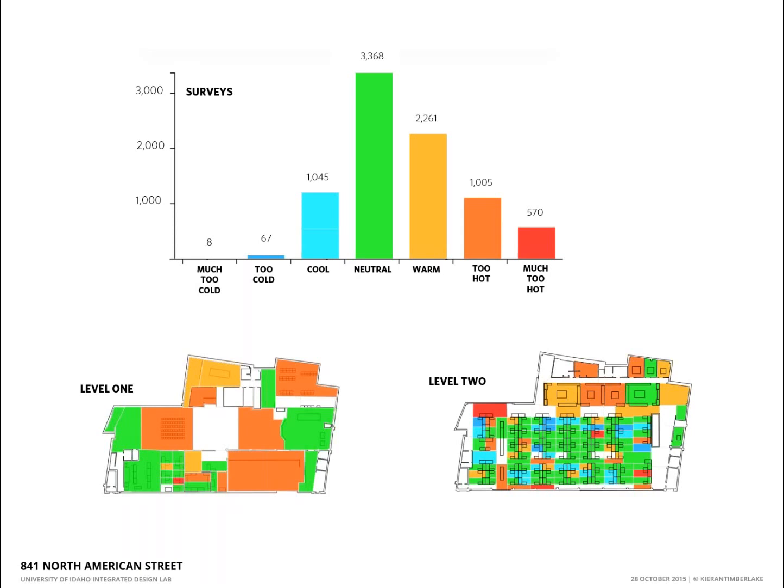And the finding that you're seeing these gains from the fan was not going to happen from the BMS. There were no sensor data points installed in that location. It actually happened because we had deployed a very dense network of sensors throughout the building that allowed us to measure the incoming air temperature and the air at all points when it came out of the air handling unit. So that was for us a really interesting moment. It also is one in which we found that certain modes of operation were not only completely invalid, but other modes of operation were entirely reasonable.